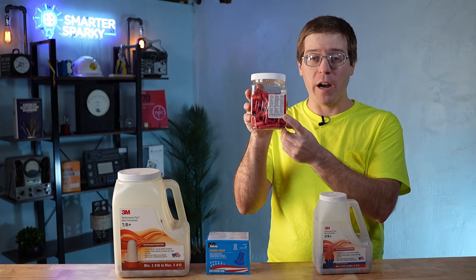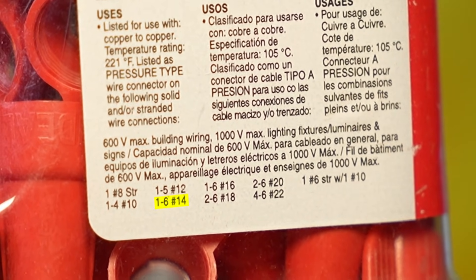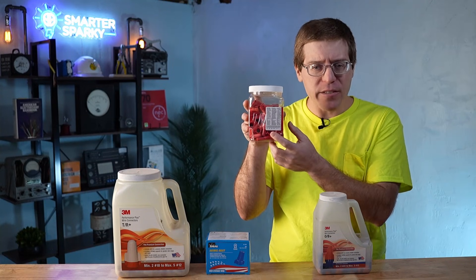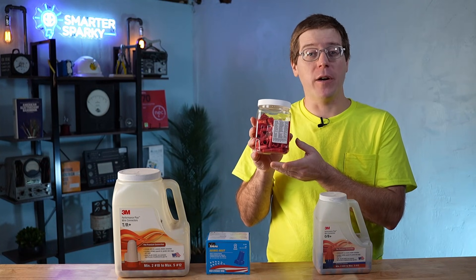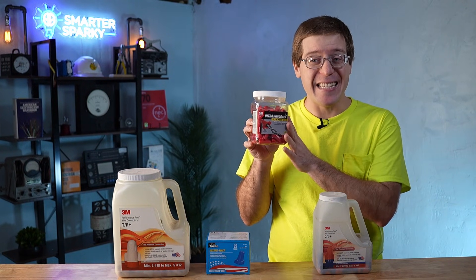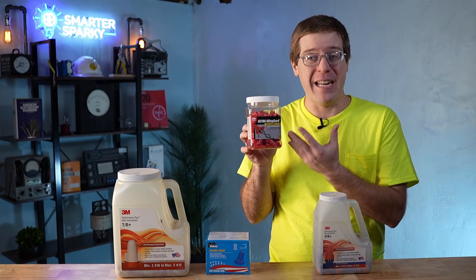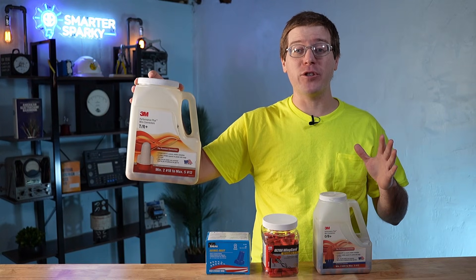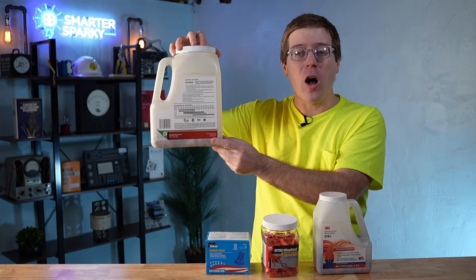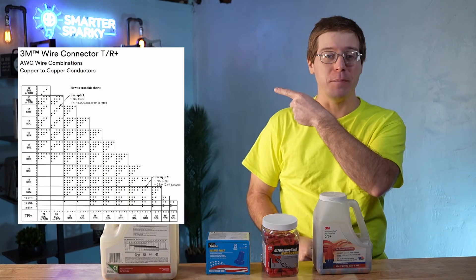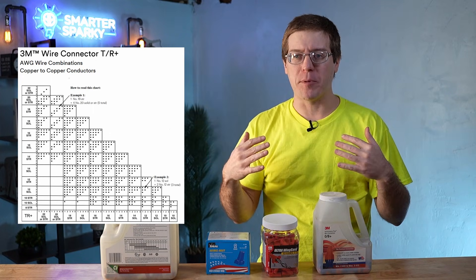For example, these wire nuts are good for 1 to 5 number 12 gauge wires, or 1 to 6 number 14 gauge wires, and so on. But what if you need to splice a 12 gauge wire to a pair of 14 gauge wires? Unfortunately, these DIY grade wire nuts can leave it ambiguous whether or not that combination is acceptable.